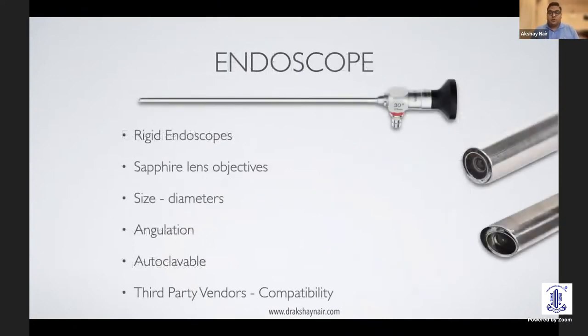And finally, the endoscopes. We prefer to use rigid endoscopes that have a scratch-free sapphire lens objective at the end. They are available in different sizes, either 2.4 mm, 2.7 mm, 4 mm, multiple sizes based on the diameter that you need to use. In pediatric cases, you might want to use small diameters. In adults, you can use a 4 mm diameter or larger ones. The angulation, as you can see from the side, can either be an end-on flat 0 or even a 30-degree angulation. These are also autoclavable.